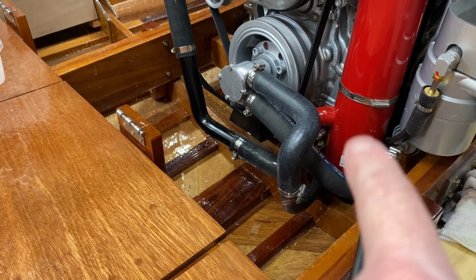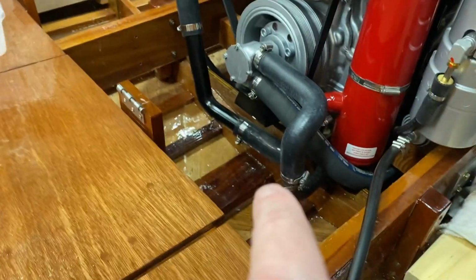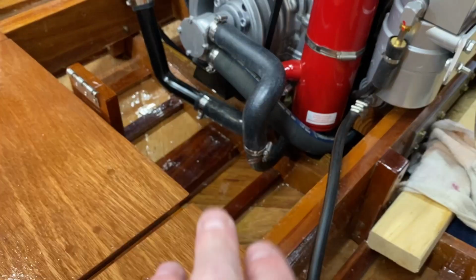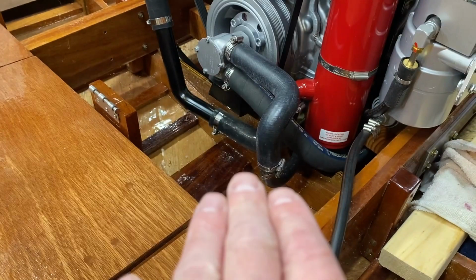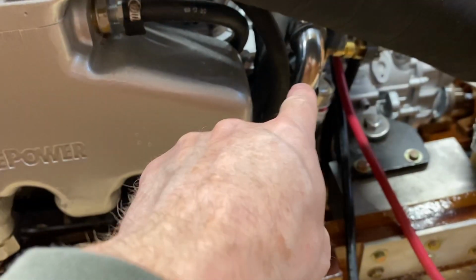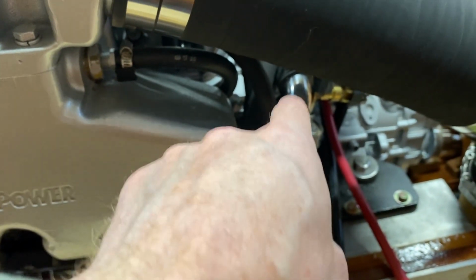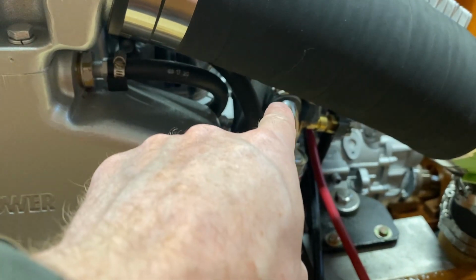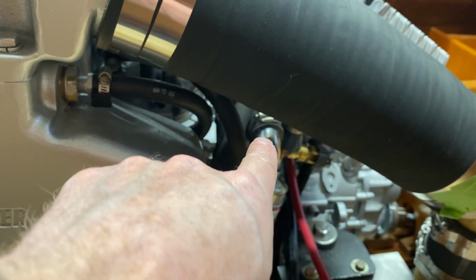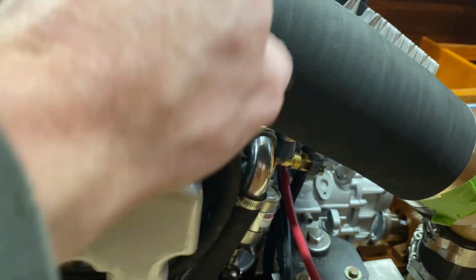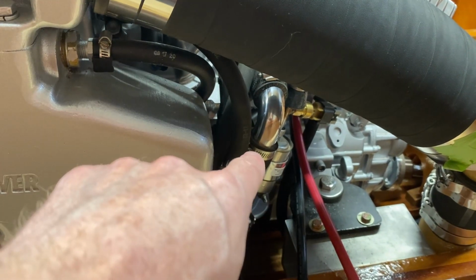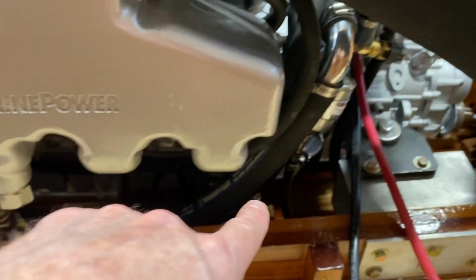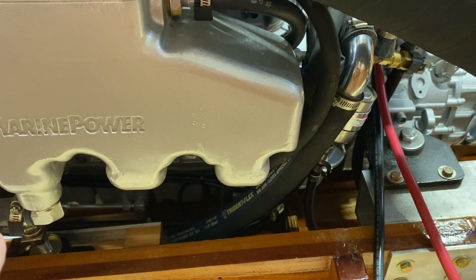That one hose is the one that comes out the bottom of the heat exchanger. Empty that bucket, then put the container under there because more water will come out, and let that drain down. Then take this fitting off, this elbow, pull it out, stick the shop vac in the output of the engine transmission oil cooler, make sure that's sucked out good, and stick the shop vac in this side to make sure it's good and cleaned out of water.